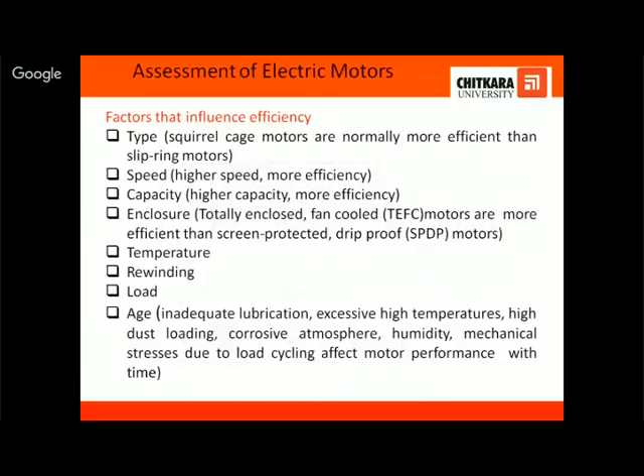Now, these are some of the parameters which affect the efficiency of the motor: what type of motor we are using, what the speed of the motor is, what the capacity is, what kind of enclosure we have used, and what the operating temperatures are, whether the motor is original or we have done rewinding of the motor, what the loading conditions of the motor are, and what the age of the motor is. More or less, age further depends on the maintenance part only. That age is, you can say, a function of the lubrication.